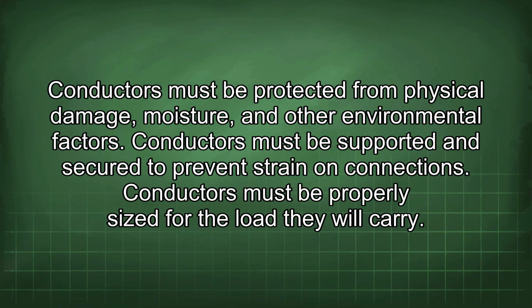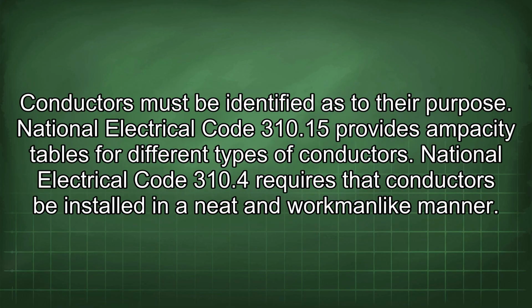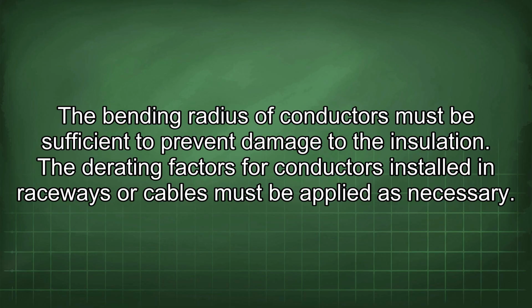Conductors must be protected from physical damage, moisture, and other environmental factors. Conductors must be supported and secured to prevent strain on connections. Conductors must be properly sized for the load they will carry. Conductors must be identified as to their purpose. National Electrical Code 310.15 provides ampacity tables for different types of conductors. National Electrical Code 310.4 requires that conductors be installed in a neat and workmanlike manner. The bending radius of conductors must be sufficient to prevent damage to the insulation. The derating factors for conductors installed in raceways or cables must be applied as necessary.